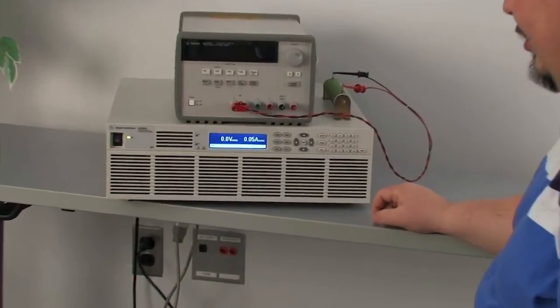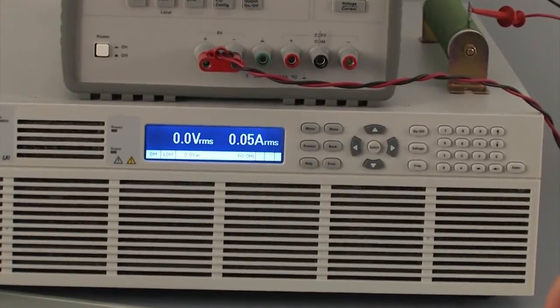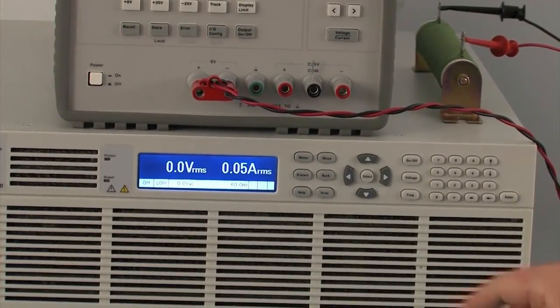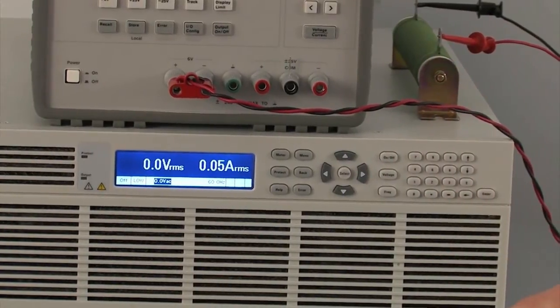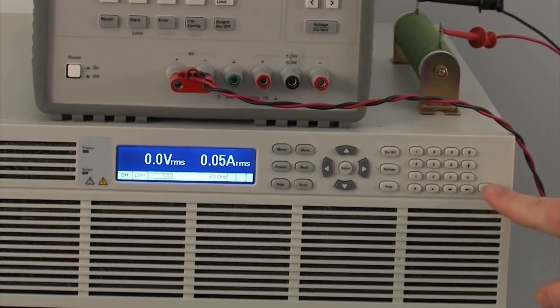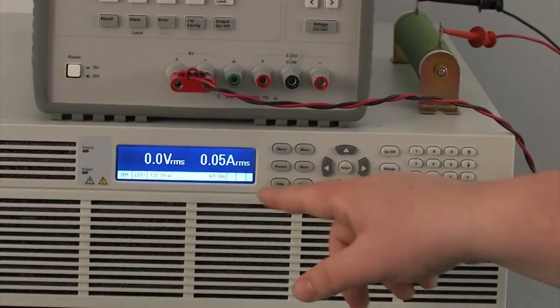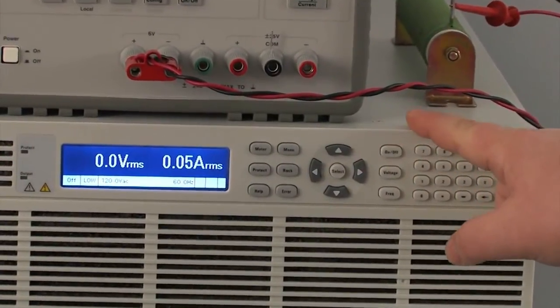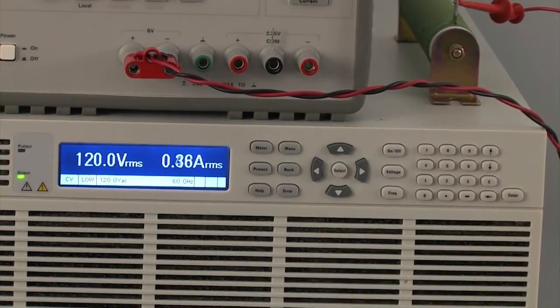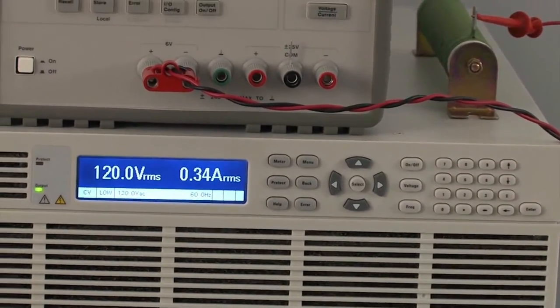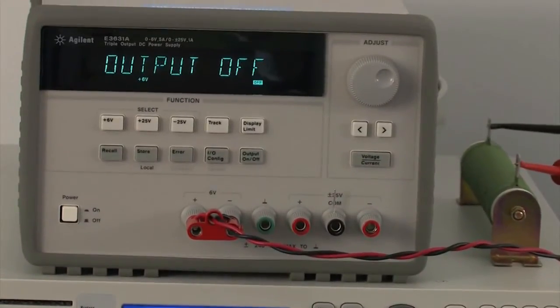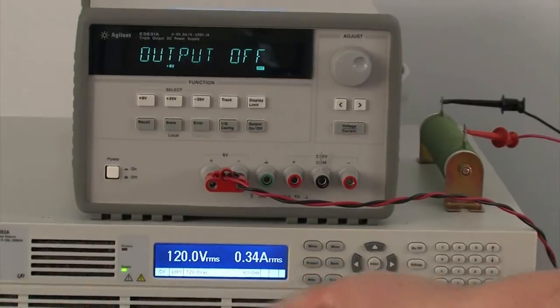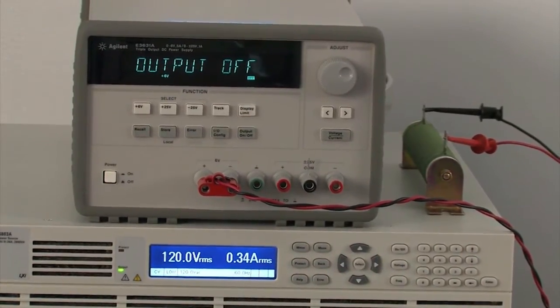So when you start the AC source, the first thing we're going to do is get our DUT running. We're going to set the voltage. This is set up to work in the US, so it's a 120 volt unit and 60 hertz. It's already set to 60 hertz, so we'll leave it at that. I'm going to turn the output on and you can see my DC power supply is turning on. Now that's on, you can see that it's 120 volt output and it's measuring about 340 milliamps RMS current draw.